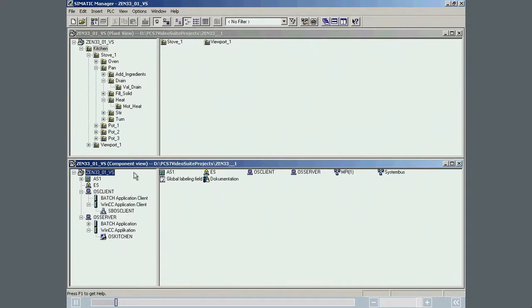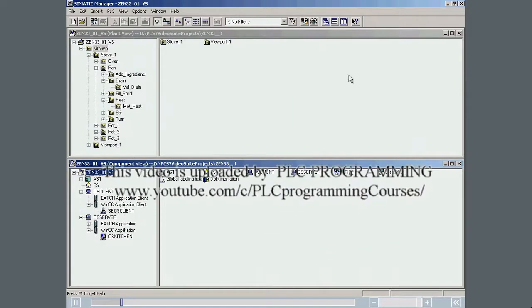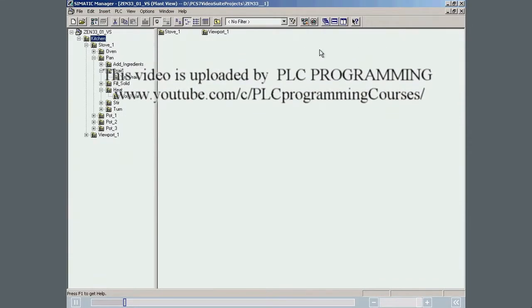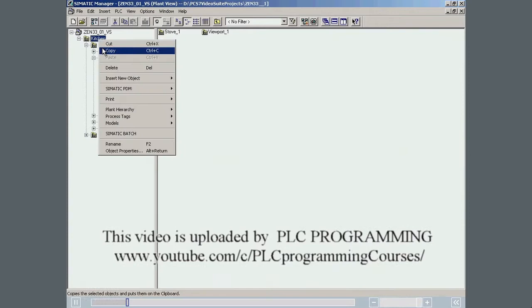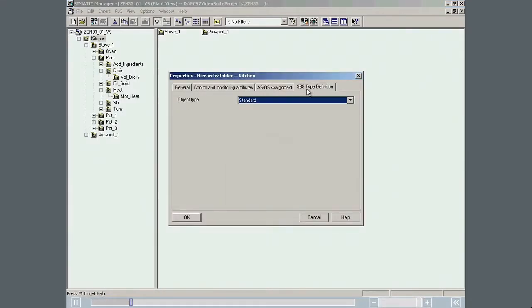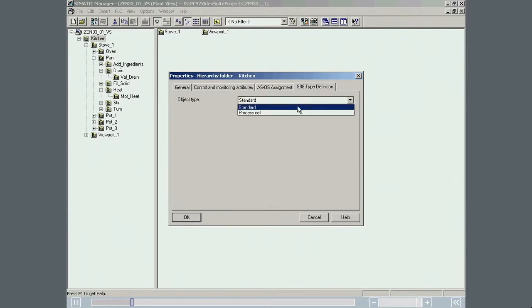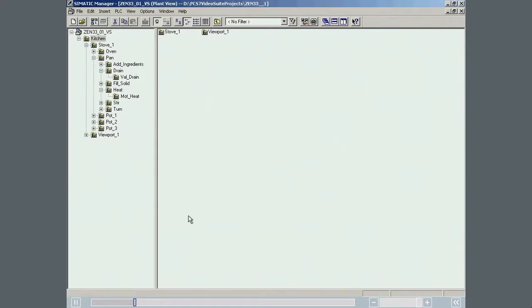The first step involves specifying the types of the objects relevant to Simatic Batch in the Simatic Manager. This is done in the Properties dialog of each Batch object. First the Kitchen folder is marked as a process cell. The Kitchen folder is now shown in green to indicate it is a Simatic Batch object.